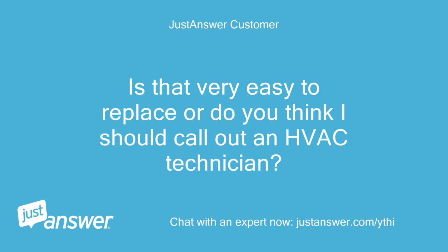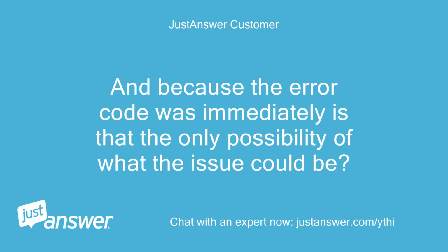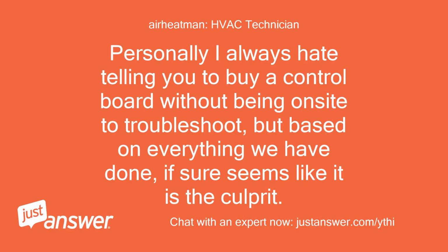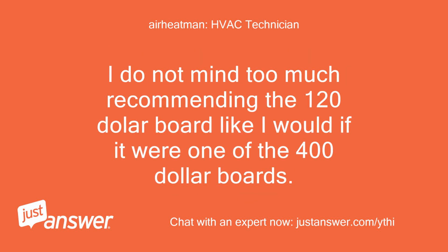Is that very easy to replace, or do you think I should call out an HVAC technician? And because the error code was immediate, is that the only possibility of what the issue could be? Personally, I always hate telling you to buy a control board without being on site to troubleshoot, but based on everything we have done, it sure seems like it is the culprit. I do not mind too much recommending the $120 board like I would if it were one of the $400 boards.